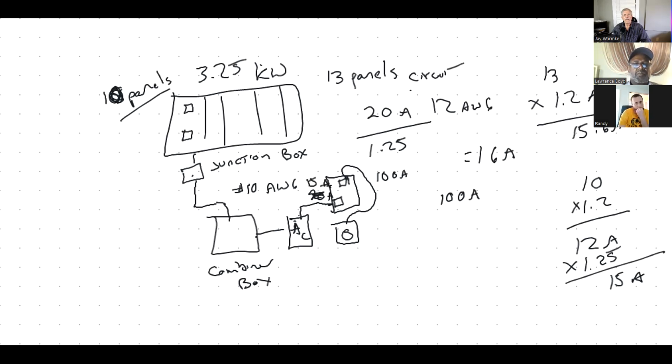Well, that's well within the 120% rule. I've got 15 from my inverter, 100 from the grid. So I'm at 115, which is less than 120. So that system is designed okay as far as the NEC is concerned. All right. Does that make sense what we've done here?